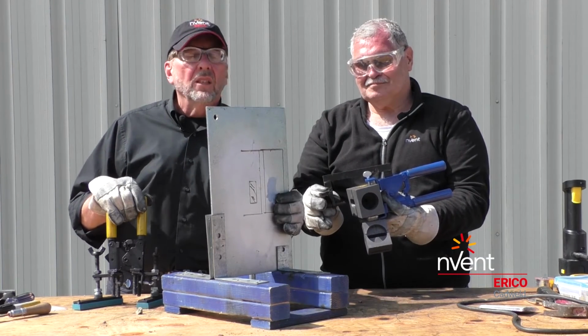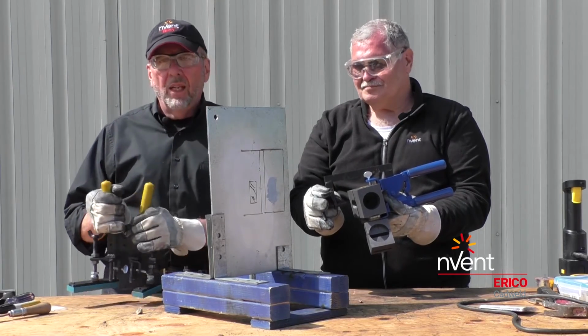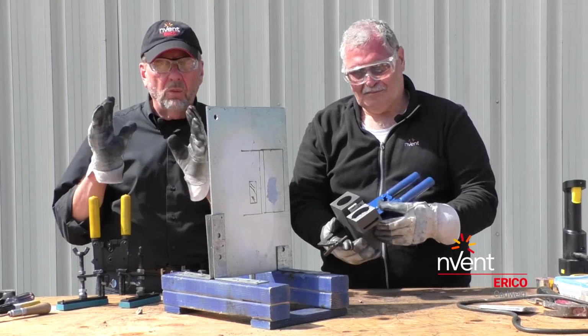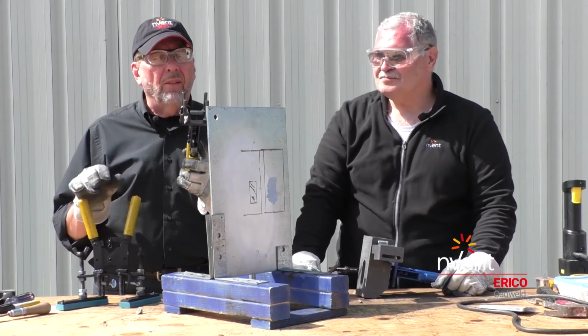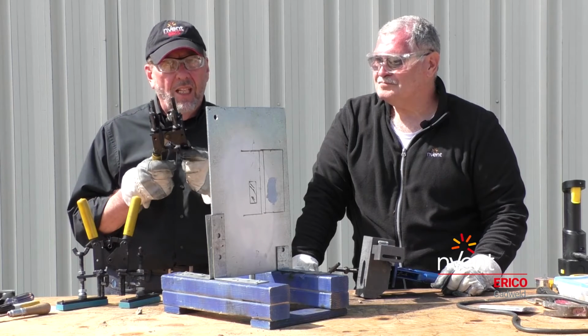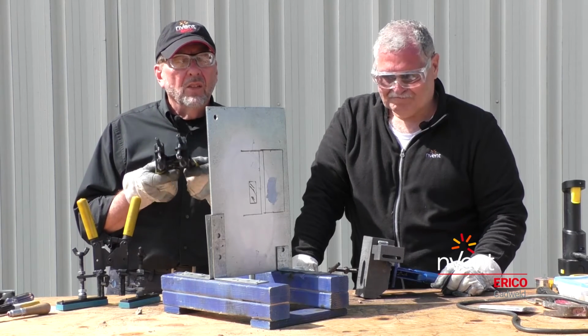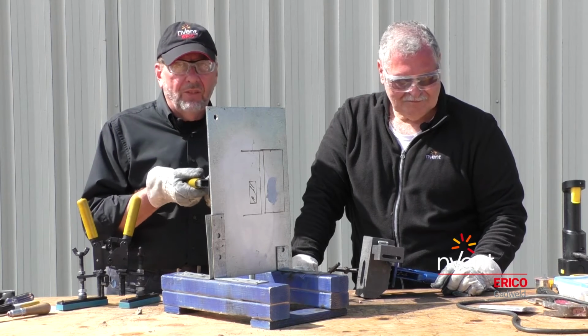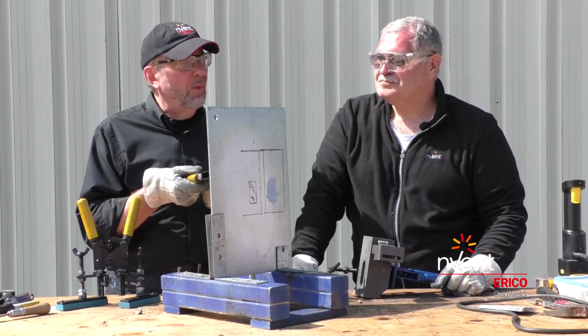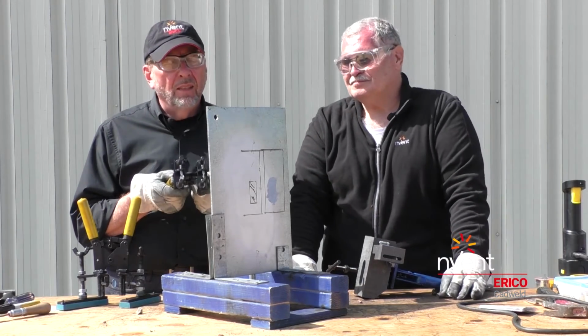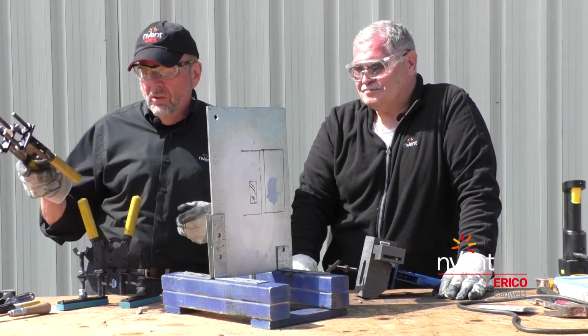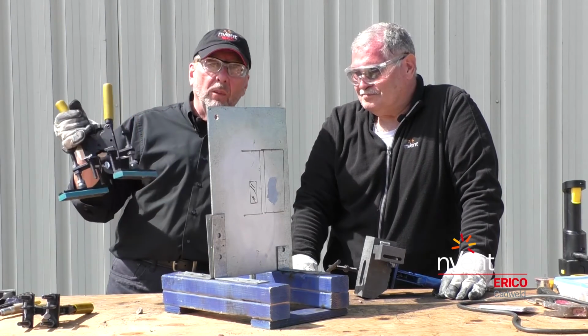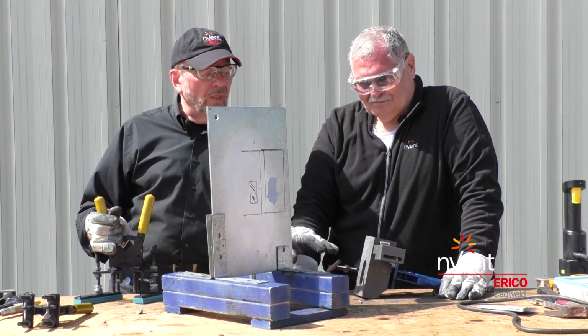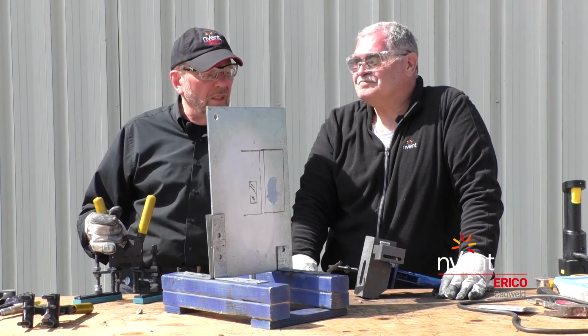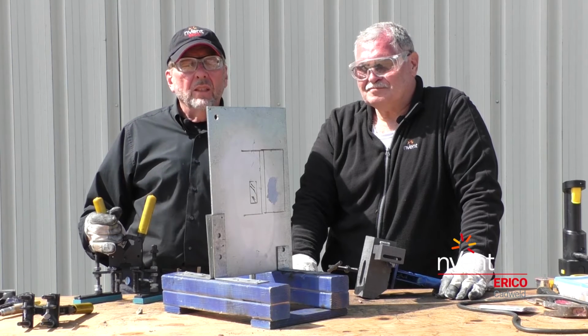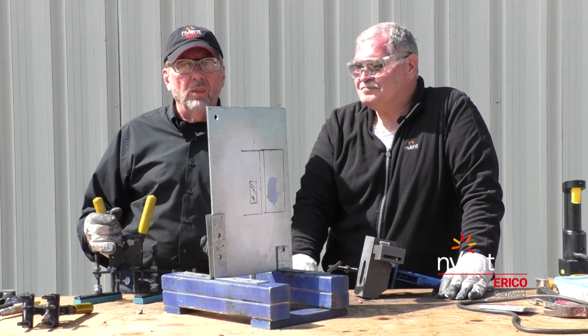So this works very much like a C-clamp, and to use this I have to have access to the back of the steel. So if this was a beam, I'd be going to the flange. The magnetic handle clamp would work in the web, in between the flanges. It's very important to point out that either one of these molds would at least have to have the standard L160. So I can use that, but then I have to hold the mold in place and put the cable into the mold, hold the mold, and put the welding material in it, and that can be a daunting task. So having something a little bit more expensive like the B396, or something fairly inexpensive if I have access to the back of the steel, or I can use the B134, certainly makes connections to steel very much easier.